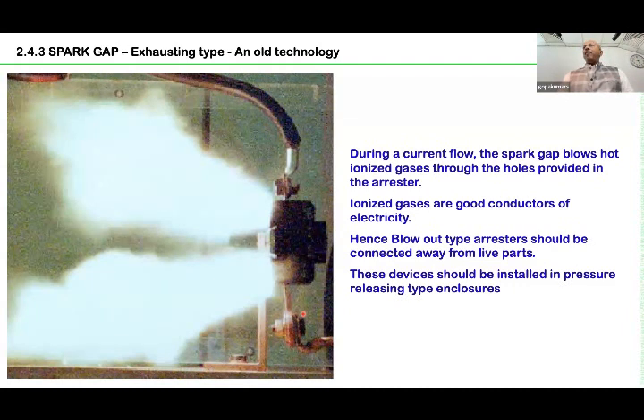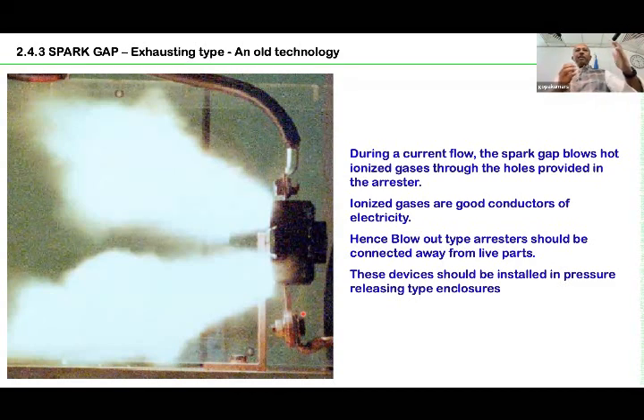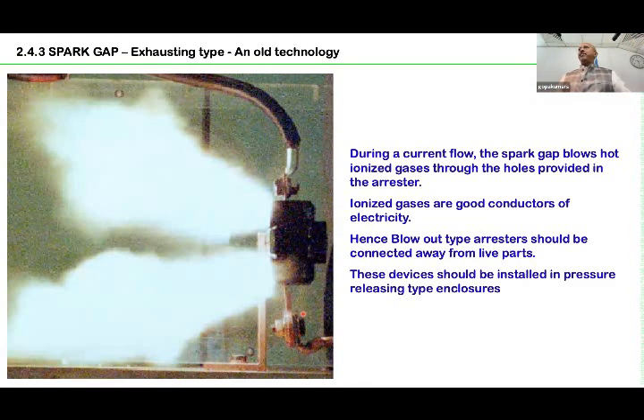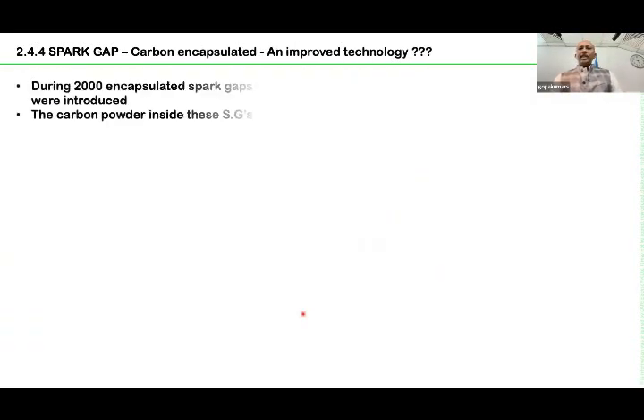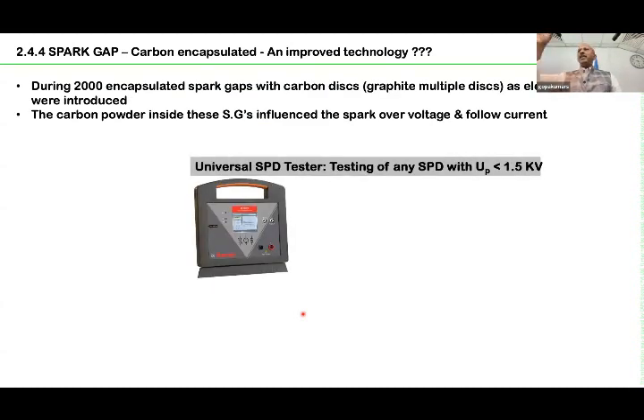And one more device available is, for example, the encapsulated device. When we started selling the device during 1997, almost all spark gap type SPDs were blowout type. Blowout type means you can be sure that if the SPD operated, and you look at its backside, maybe half a meter, then the entire place is black because of the arcing. It is designed for that. After that, a new technology came, which is called encapsulated. Encapsulated means a completely sealed SPD. One of the first technologies which came is the carbon spark gap. Carbon means there is a gap, but the material used, previously it was tungsten, then one of the manufacturers changed it to carbon, a graphite plate.